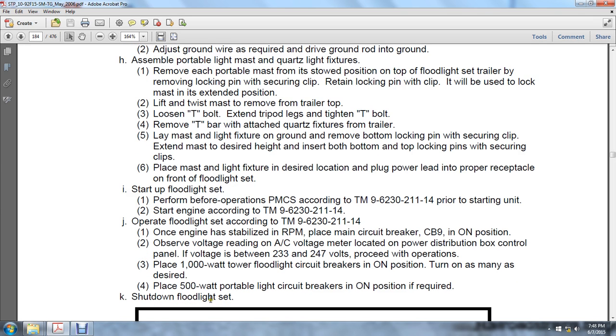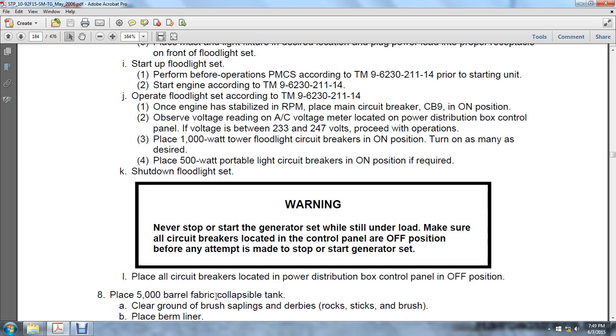If required, shut down the floodlight system. Never stop and start the generator set while the set is still under load. Make sure that all circuit breakers located in the control panel are in the off position before any attempt is made to stop or start a generator set. Place all circuit breakers located in the power distribution box control panel off.